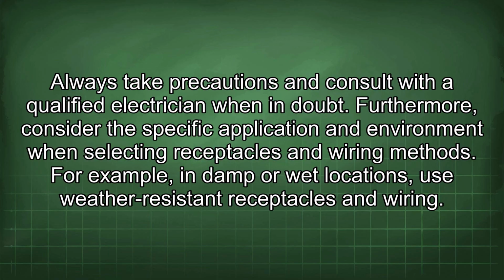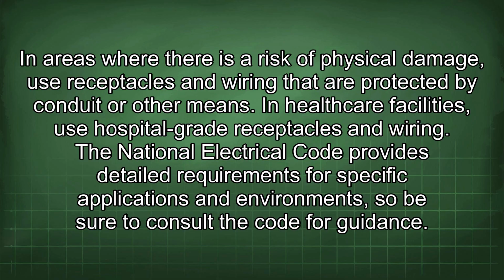Furthermore, consider the specific application and environment when selecting receptacles and wiring methods. For example, in damp or wet locations, use weather-resistant receptacles and wiring. In areas where there is a risk of physical damage, use receptacles and wiring that are protected by conduit or other means. In healthcare facilities, use hospital-grade receptacles and wiring. The National Electrical Code provides detailed requirements for specific applications and environments, so be sure to consult the code for guidance.